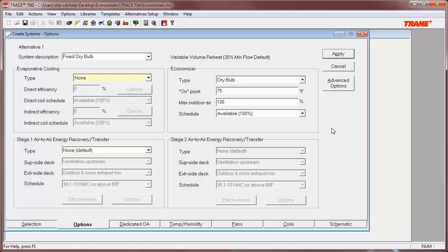As related to ASHRAE Standard 90.1, this on point will vary depending upon the climate zone the building is located in, but will vary between 65 and 75 degrees Fahrenheit for the United States. It is important to note that all economizer control methods in TRACE are modulated and integrated, meaning that once the damper reaches its high limit as set in the max outdoor air field, mechanical cooling will be used to satisfy the remaining load. This satisfies the requirement of integrated control specified by Section 6.5.1.3 of Standard 90.1.